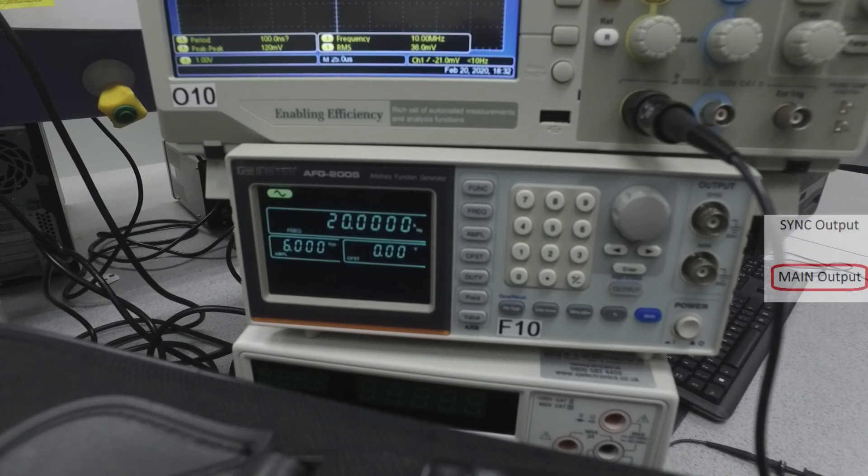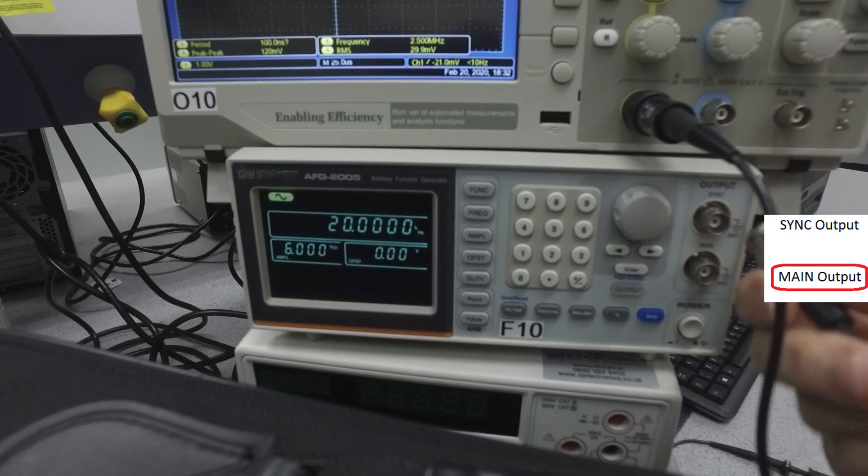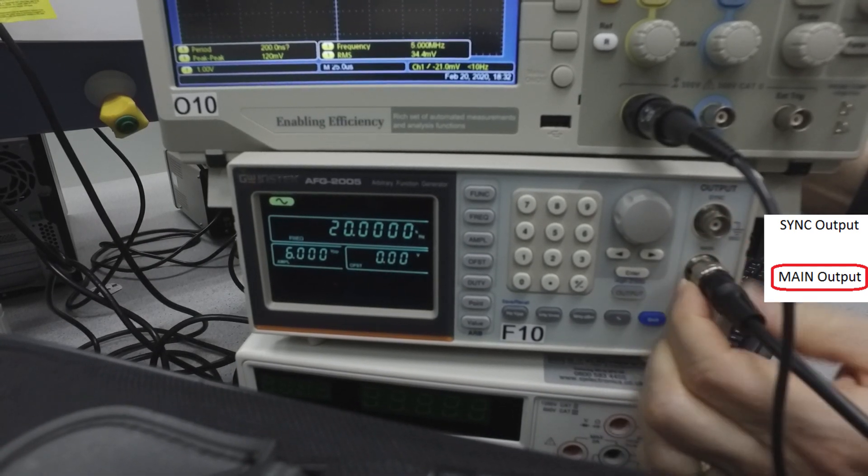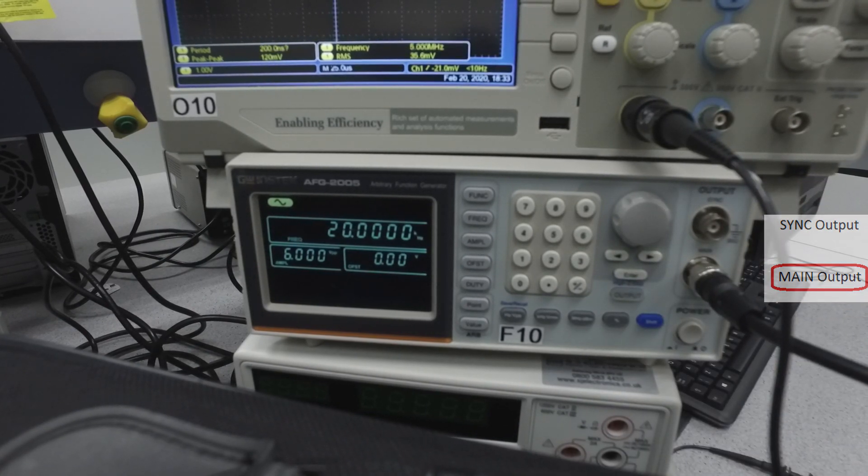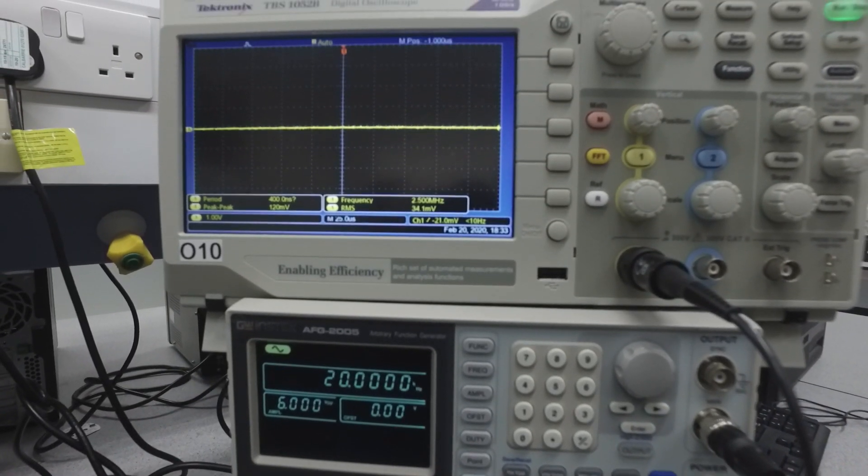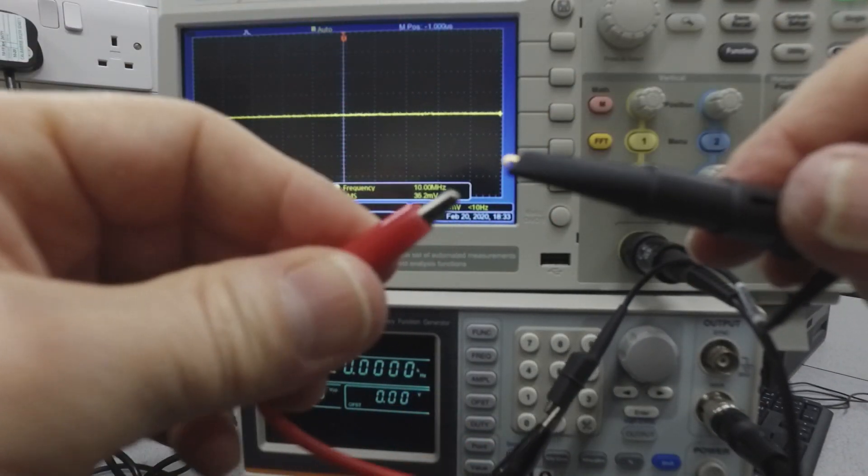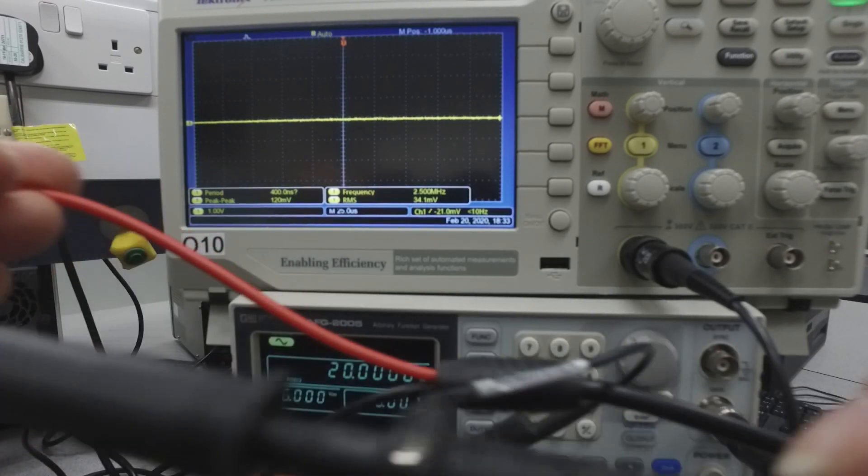So what we'll do is, again, looking at the function generator, which we've set up the values for, we'll apply this to the main on the output. There's two options here. The sync, for synchronizing, and the main, for the main output. Now, if we want to do this in a cheap and cheerful way, we can literally just connect the return lead of the signal generator to the return lead of the scope. Get a better connection in there. And the signal lead of the function generator to the signal probe of the scope. And that's the only connection you'd need for direct measurement.